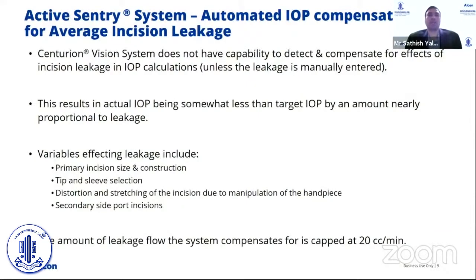The system also provides automated IOP compensation for average incision leakage. With the help of active irrigation and the pressure sensor, the system is able to calculate the amount of average incision leakage during surgery and compensate for it. Currently, surgeons either increase IOP to compensate or manually enter incision leakage — now the system handles this automatically. Variables include primary incision size and construction, tip and sleeve selection, distortion during surgery, and leakage through secondary side port incisions. The leakage compensation is capped at 20 cc per minute to ensure stable IOP.